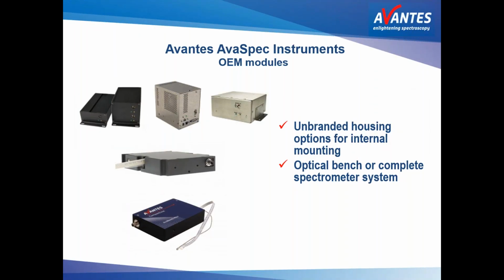And as an OEM component supplier, we can cover all aspects of the instrument design, including the enclosure. We have a couple enclosures as examples. So any of our spectrometers can be housed in a kind of black box approach, either branded or unbranded. These all include easy mount flanges for easy integration into the instrument machine that you're building. And some customers actually use their own electronics. So if you would just like to use our optical bench and mate it to your electronics, that's also possible.